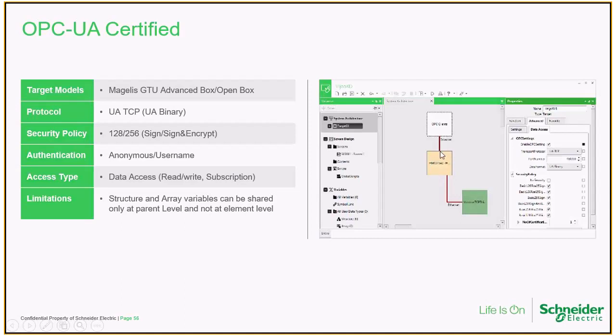Using this HMI as a gateway, it will enable the OPC UA server, and the customer's cloud system will act like an OPC UA client. So whatever data is available in the PLC on RS485, I will use the HMI as a converter, converting the RS485 or RS232 data to Ethernet enabled data on the OPC UA protocol.